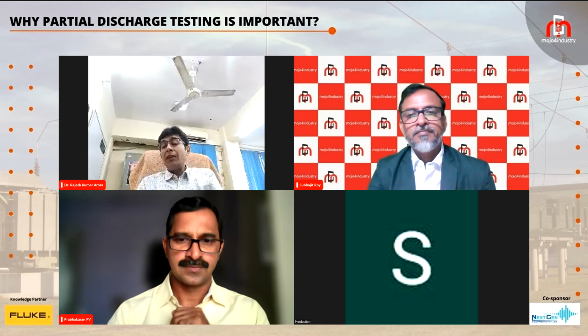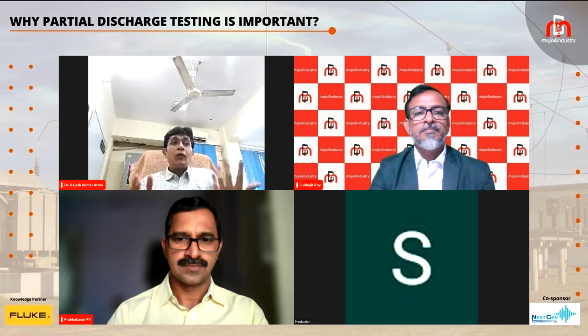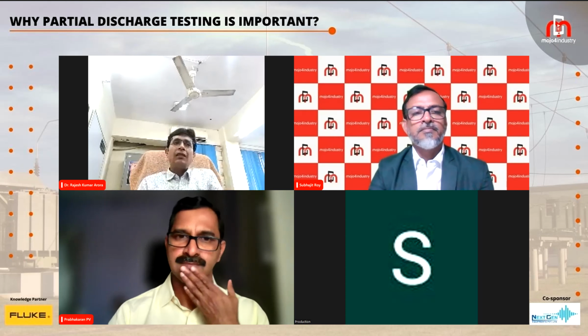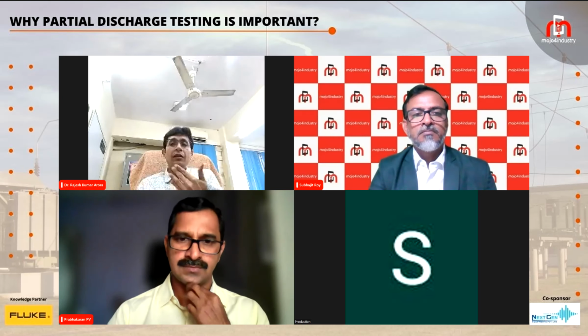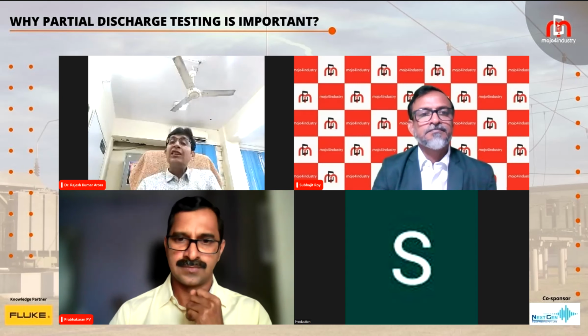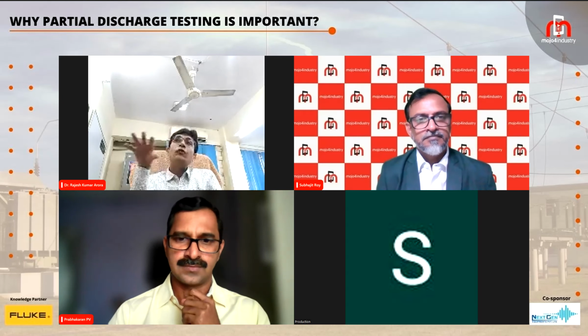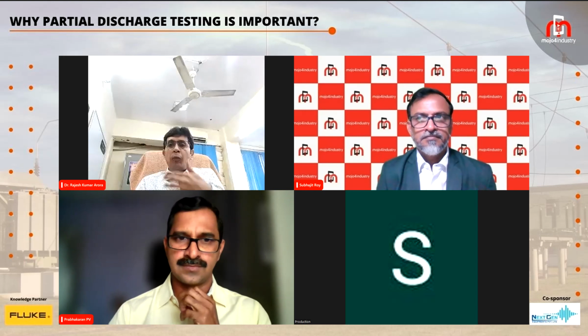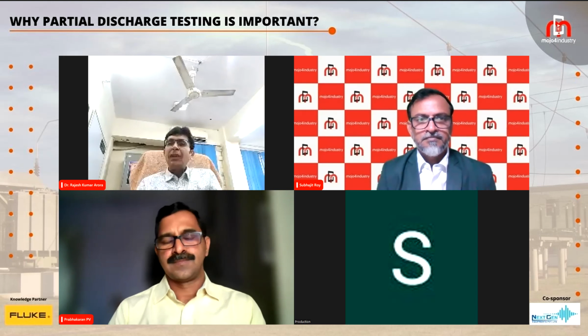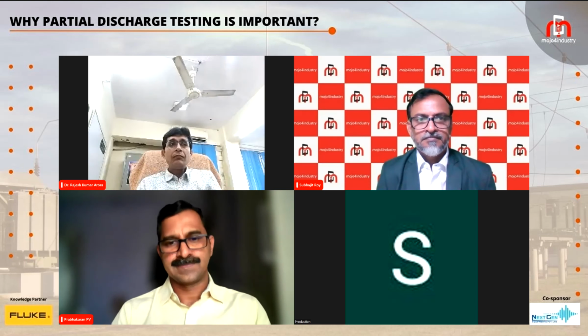This was already explained very well by Mr. Prabhakaran of Fluke. Types of PDs, there are 4 types. It is corona, it is arc, it is surface discharge, and last but not the least, it may be due to voids. And voids usually happen during the manufacturing process, from poor workmanship or some ingress of impurity during manufacturing. When we talk about the causes, the reasons for this partial discharge, it may be due to moving particles, it may be some fixed particle, it may be due to protrusions, it may be due to floating particles, and finally it may be through some voids.